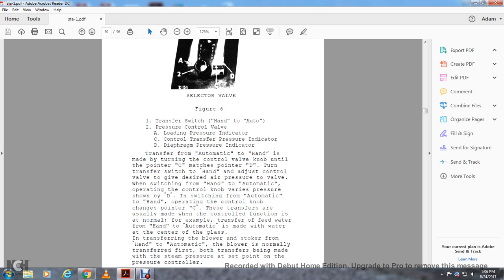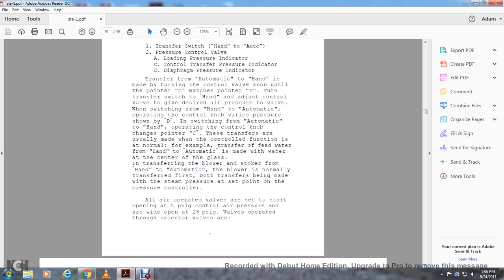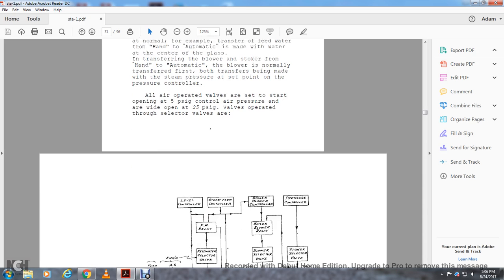For example, the transfer of the feed water from hand to automatic is made with water at the center of the glass, and then transferring the blower and stoker from hand to automatic. The blower is normally transferred first, but the transfer is made with the steam pressure at the set point on the pressure controller. All air operated valves are set to start opening at 5 psi control air pressure and are wide open at 25 psi. Valves are operated through the selector valves.